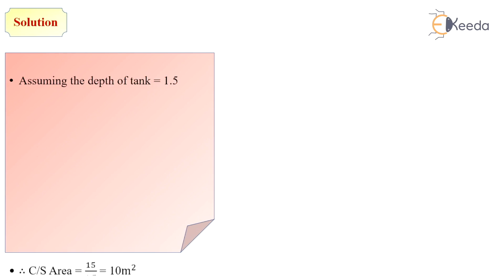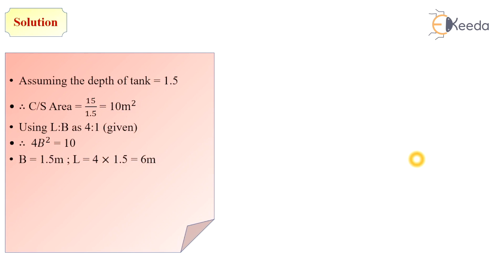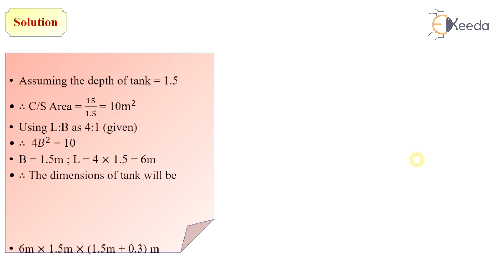Next we calculate the cross-sectional area, which equals capacity of tank divided by its depth. Assuming depth of tank is 1.5 meters, cross-sectional area equals 10 square meters. Assuming length to width ratio is 4 to 1, if width is b then length is 4b. Using the equation 4b squared equals 10, we get width equal to 1.5 meters, and length equals 4 times 1.5 equals 6 meters. So dimensions of the tank are 6 m × 1.5 m × 1.5 m with a freeboard of 0.3 meters.